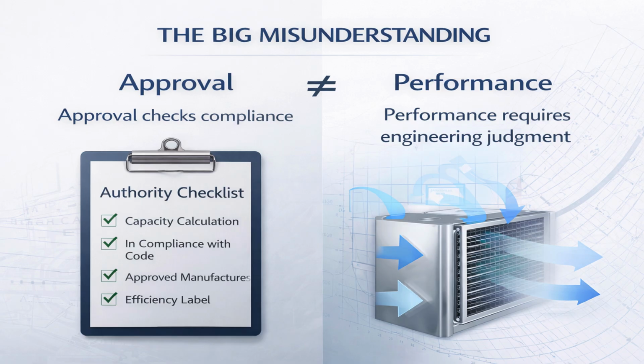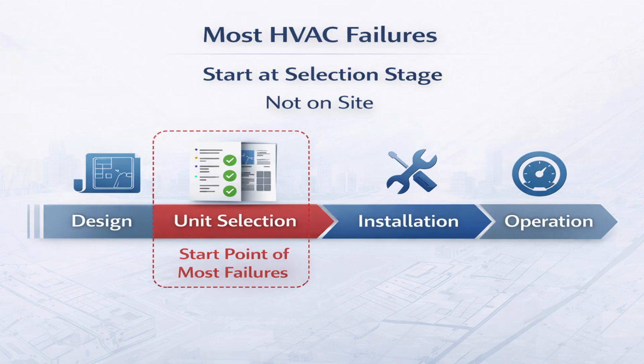True performance depends on something much deeper. It depends on how accurately we interpret the cooling and ventilation loads. How well we match unit characteristics like airflow, coil performance, and modulation to those loads. And how realistically we anticipate the building's operating patterns, schedules, and usage. This is where engineering judgment comes in, because compliance gets a system approved, but engineering decisions are what make it perform. Most HVAC failures don't actually begin on site. They usually start much earlier, quietly, during the unit selection stage.